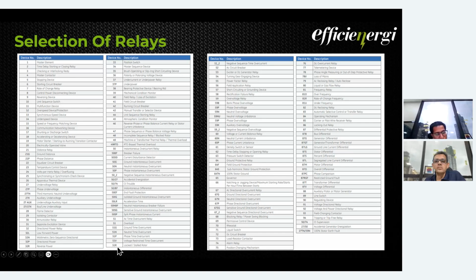Recently, I've done one data center wherein the chilled water pump is of 11 kV motors. There, I have tried to give this 51LR, but again, not implemented yet. But in other industries everywhere where 11 kV motors are there, we are using this 51LR. Then a negative sequence relay basically should be used for generator protection.